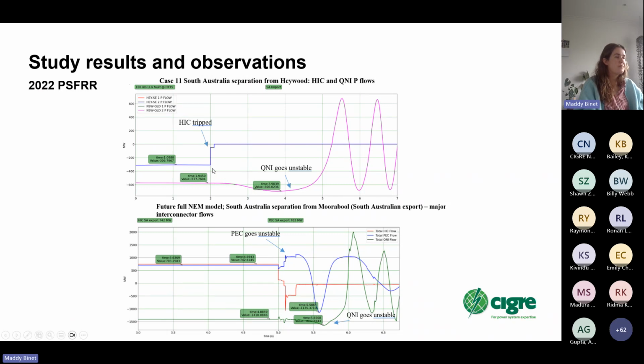So you can see here that for the pre-contingent flow, SA and Queensland are both exporting at fairly high levels, and following Heywood being tripped, QNI swings above its export stability limit and then goes unstable, and Queensland loses synchronism with the rest of the NEM.